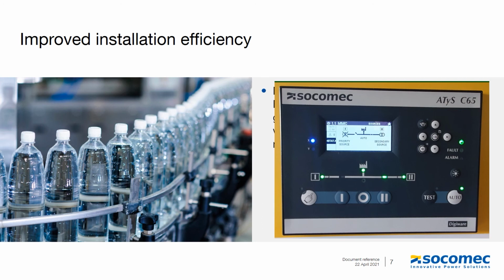By having a fail timer set above 0 seconds, as well as a return timer above 1 minute, you will leave more time for your product to determine whether your priority source is definitely lost or not, and if it is better to stay connected to the emergency power source.